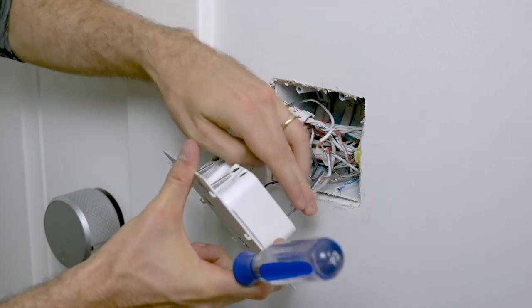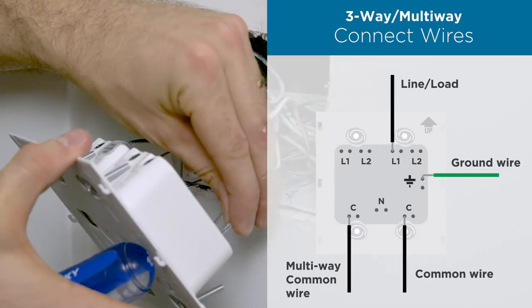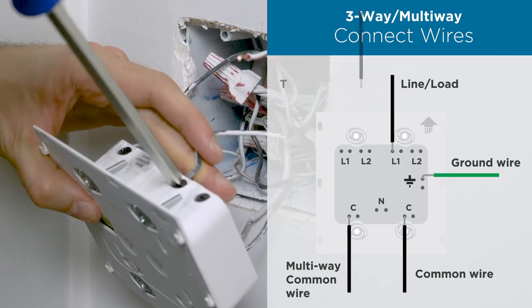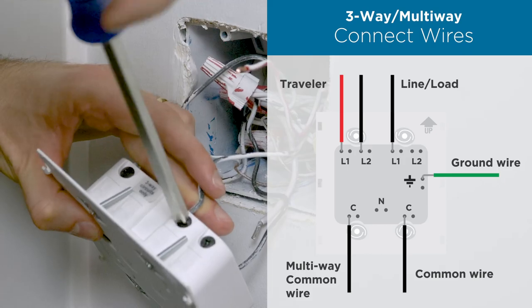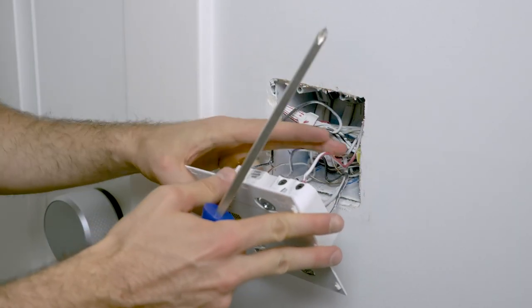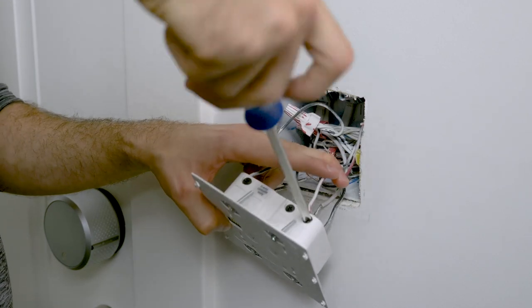Next, for the multi-way switch on the right, I'll take the common wire here and screw that in tight. I'll grab the two traveler wires. These will be going into the holes alongside the screws labeled L1 and L2. Make sure to screw them in tight and there is no exposed wire.